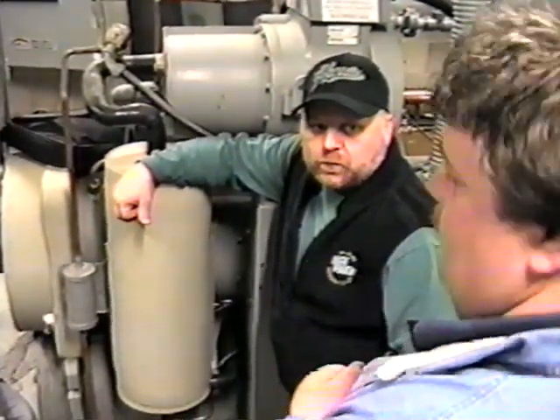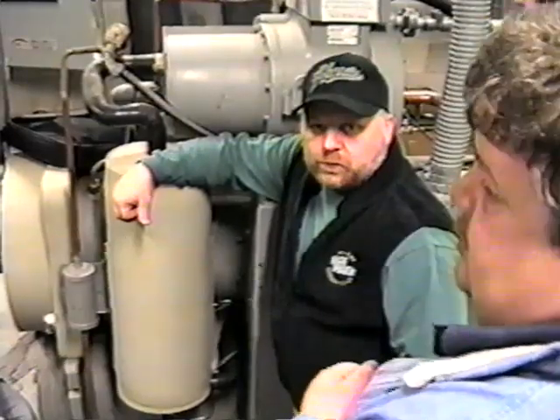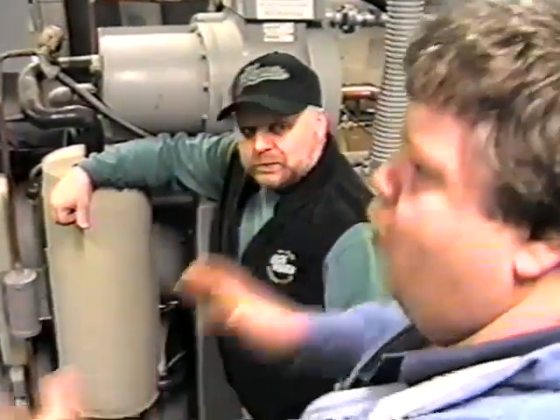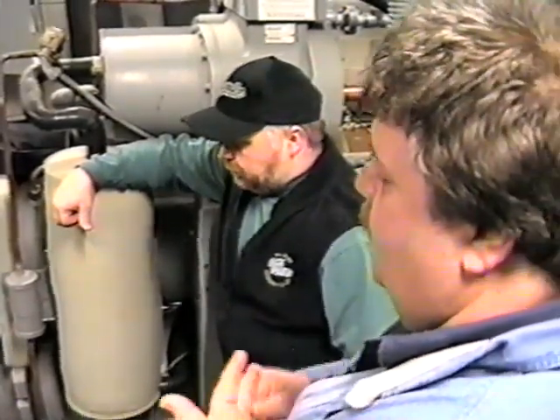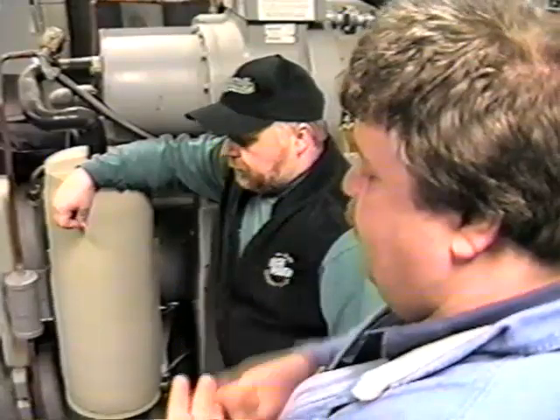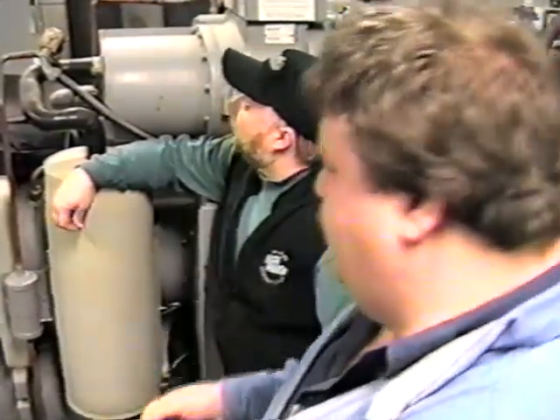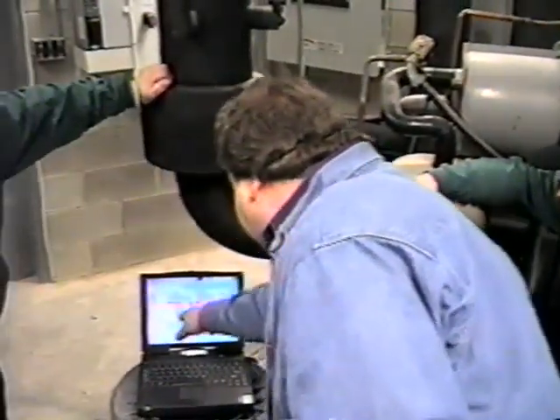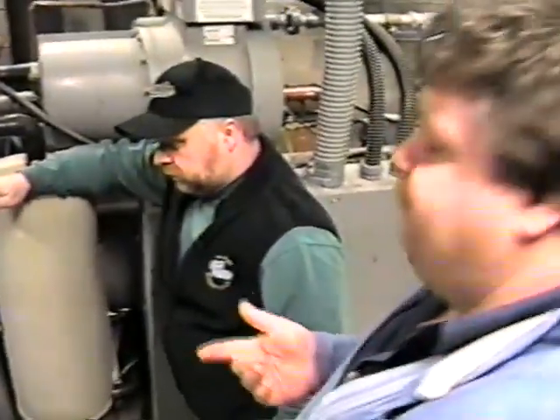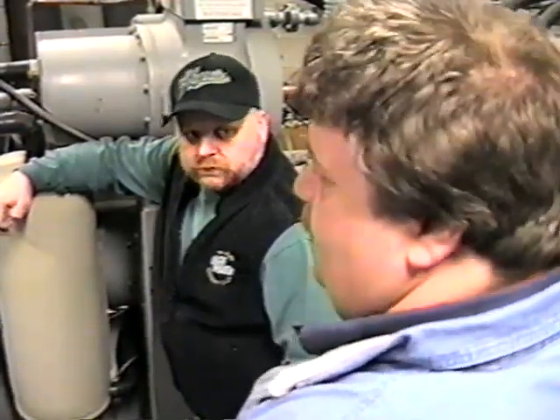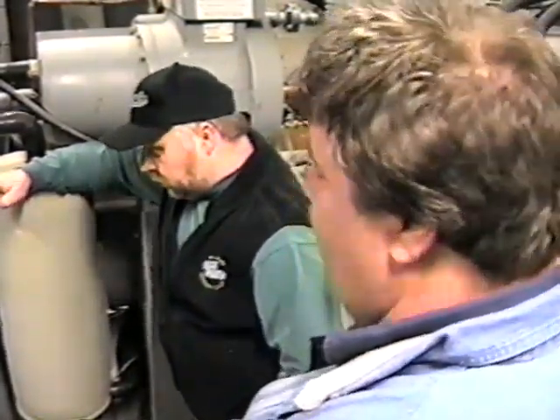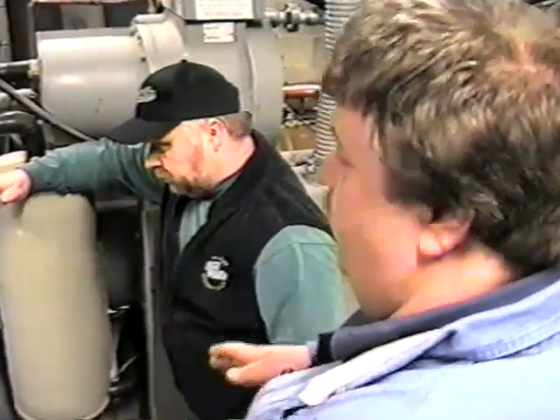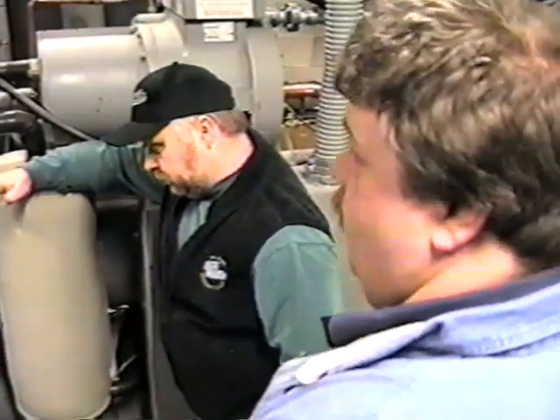We want to prove flow through the chiller other than the Carrier unit's flow switches. Those are independent of what we're doing, so we have double protection here as far as freeze protection. Once you prove the status as being high speed, through our program, we allow the chiller to be enabled. And that's through this remote control over here, the switch he was talking about. That'll let the chiller come up and run on its own controls.